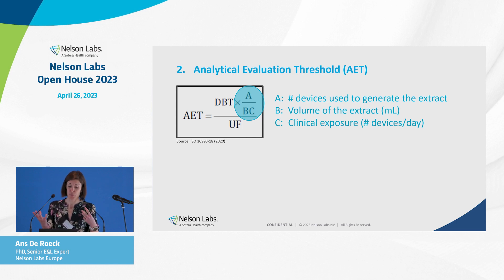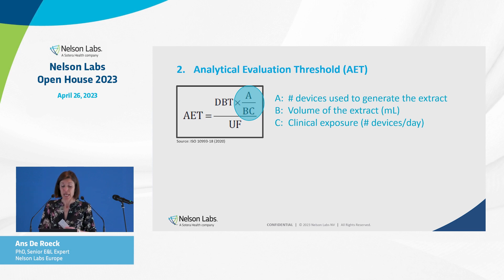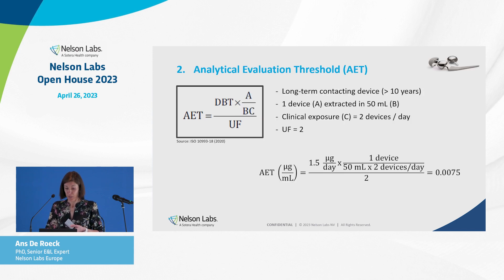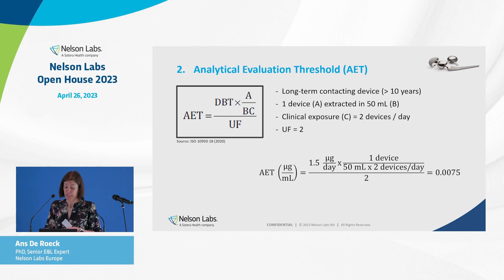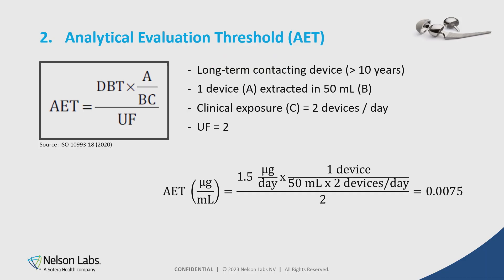The formula also includes factors A, B, and C to convert the dose-based threshold to a concentration-based threshold. A is the number of devices used to generate the extracts, B is the volume of the extracts, and C is the clinical exposure. For example: an implant in place for more than 10 years uses a DBT of 1.5 µg/day; if one device was extracted in 50 mL with a clinical exposure of 2 devices per day and an uncertainty factor of 2, you put those values into the formula to obtain a specific AET.